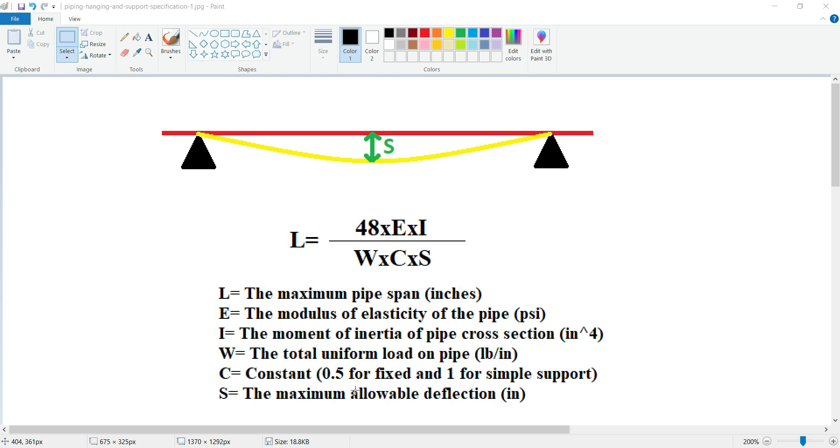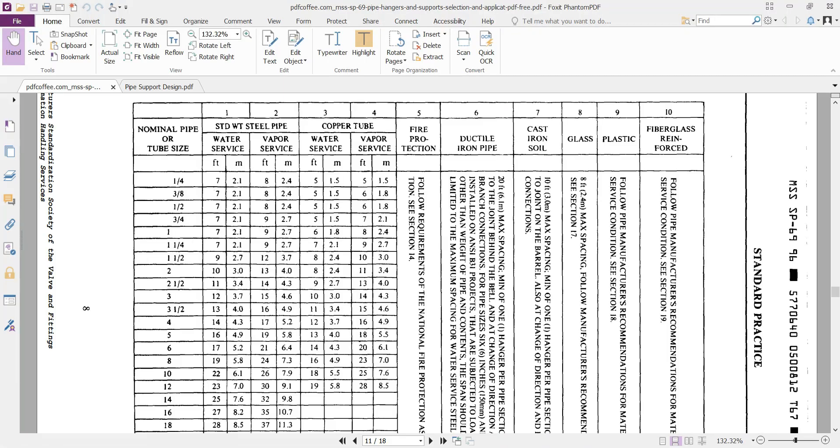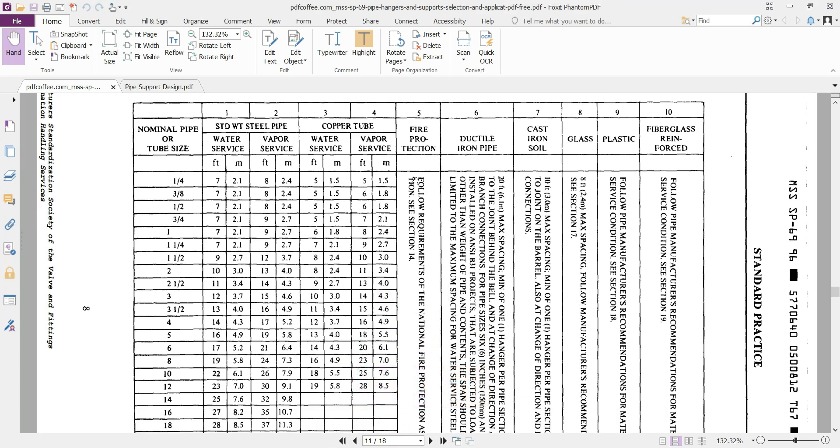This was one of the most common ways for calculating the safe pipe span, but we have other methods for understanding the maximum allowable span of piping system. One of them is standard MSS SP-69. In table 3 you can find the detail quantities for safe pipe span.